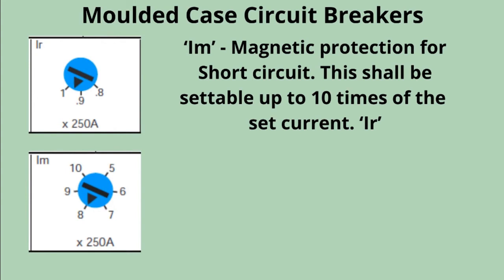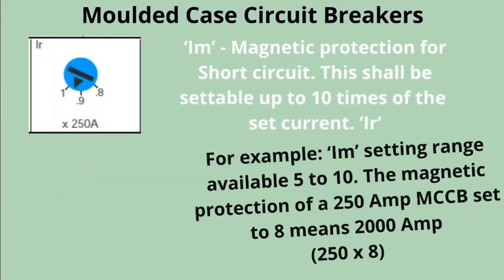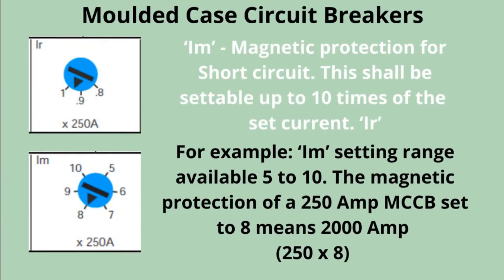Im is the magnetic protection setting for short circuit. This shall be settable up to 10 times of the set current. For example, the Im setting range is available from 5 to 10. The magnetic protection of a 250 amp MCCB set to 8 means 2000 amp — that is 250 multiplied by 8.